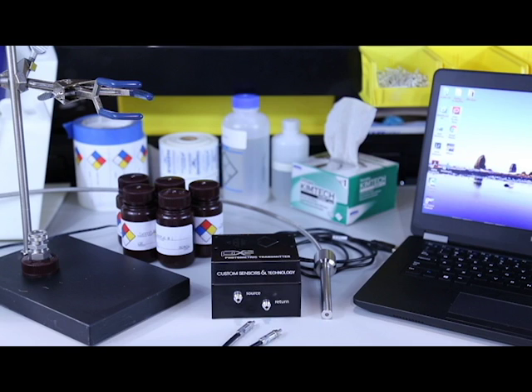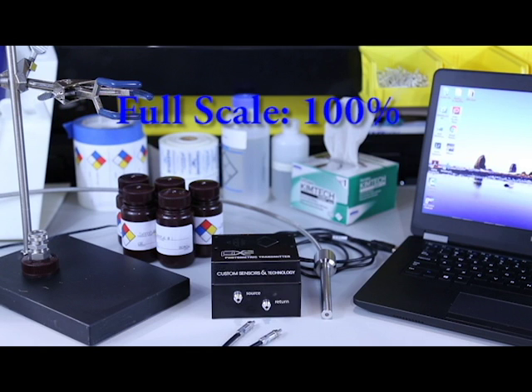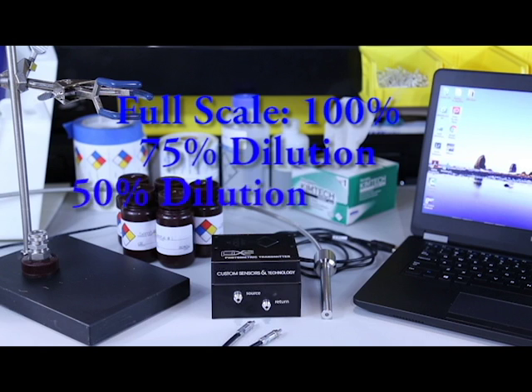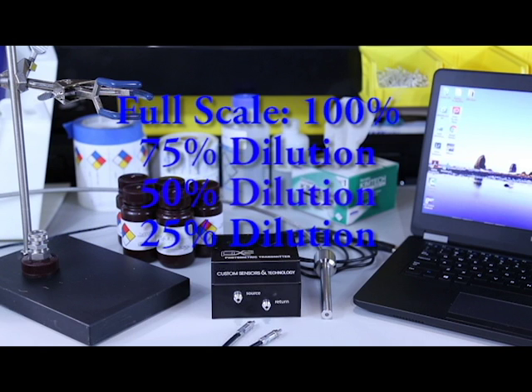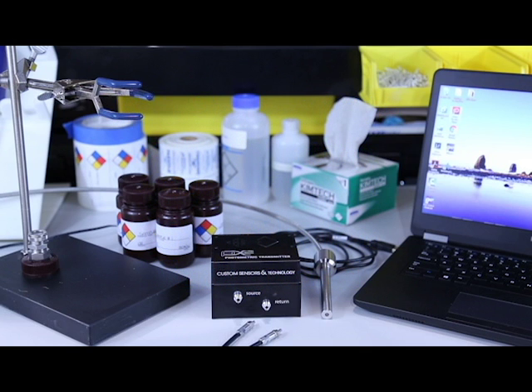To complete auto-tune, you will need the following: the appropriate PPE for handling samples, the PX2 connected to a PC with a PX2 control panel app installed, a front surface fluorescence probe, and 5 representative samples or standards in opaque bottles. I recommend using a full-scale sample, 75, 50, and 25% dilutions of full scale, and a blank with just the background. In this tutorial, I will use 125 milliliter amber Nalgene bottles affixed to the probe with a compression fitting.